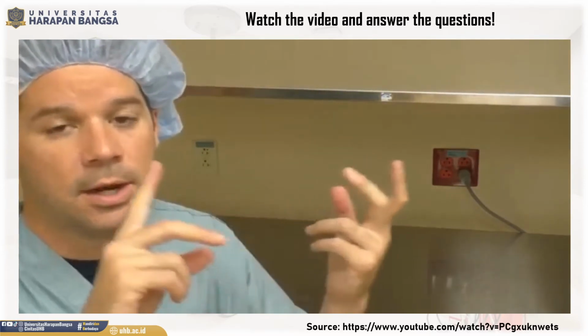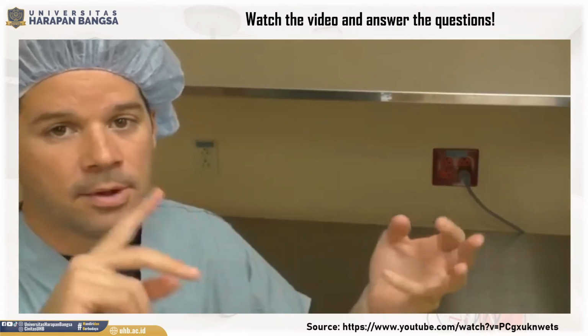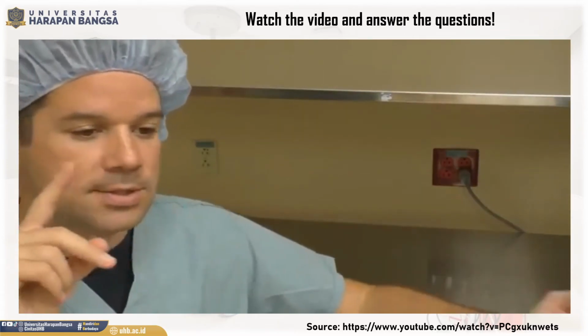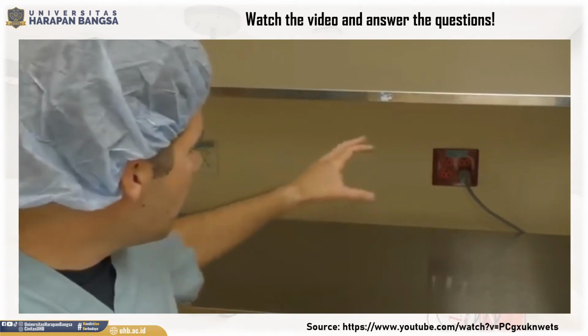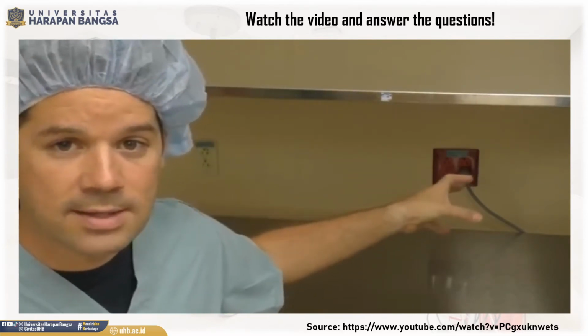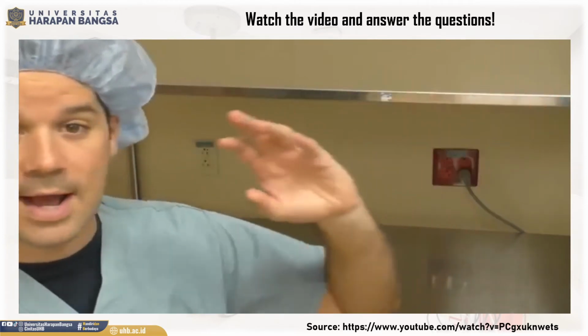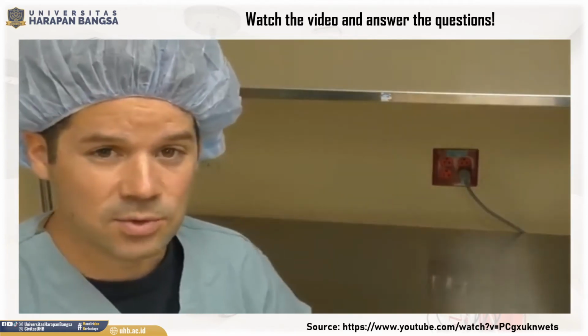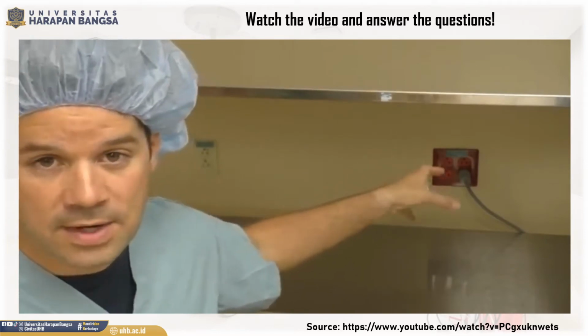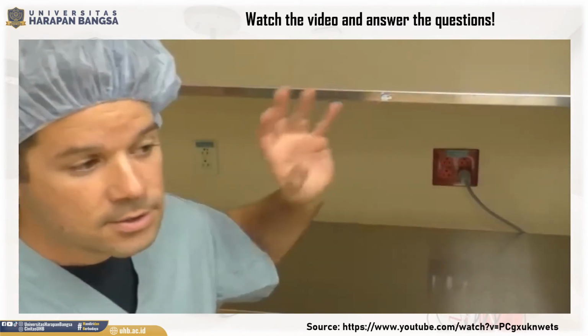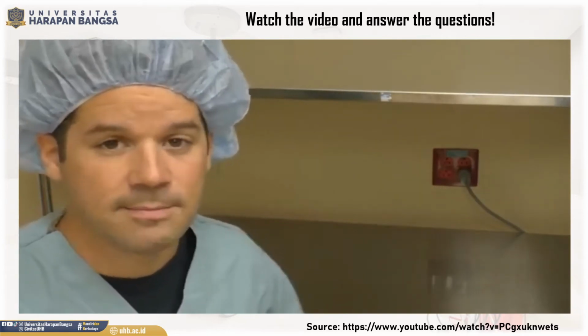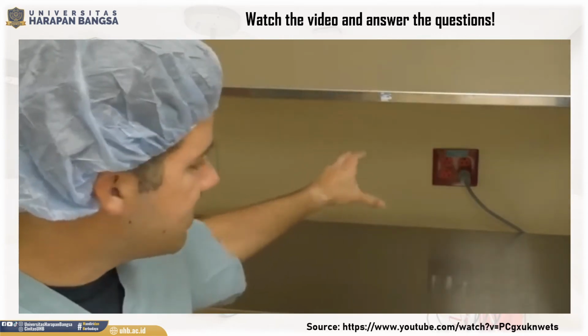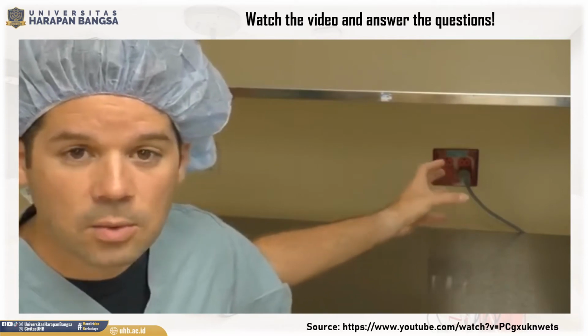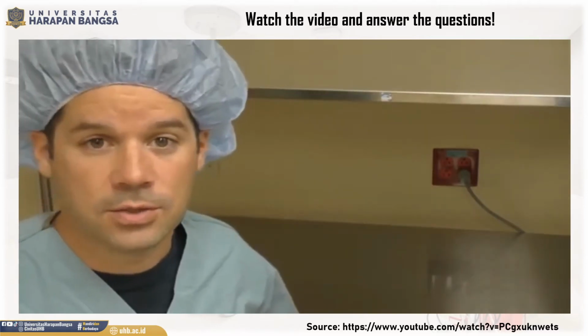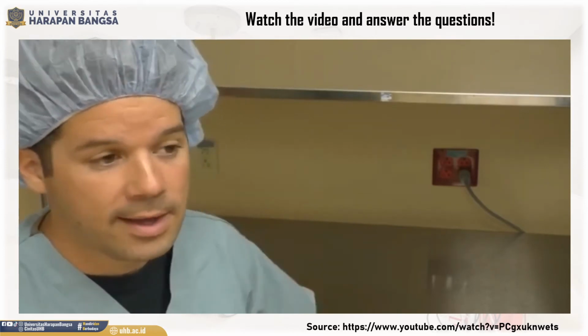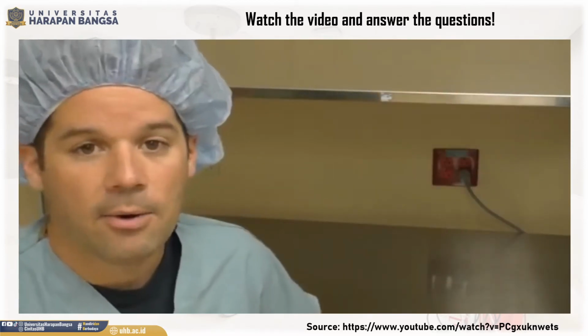Your anesthesia machine, your operating room table, everything that's on your boom, camera, light source, suction, all that stuff, because everything that's plugged into any of these red outlets inside of this room, which there are multiple red outlets placed on the walls around these rooms, all of these red outlets are directly hooked up to the generator. So if for some odd reason there's a massive power outage, these devices that are still plugged into these red outlets will keep running. So we'll be able to finish the surgery so long as we have generator power in case of a massive power outage.